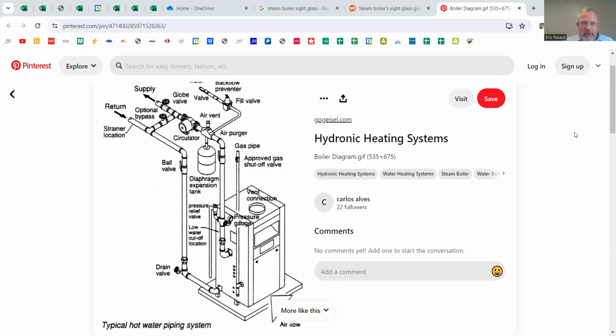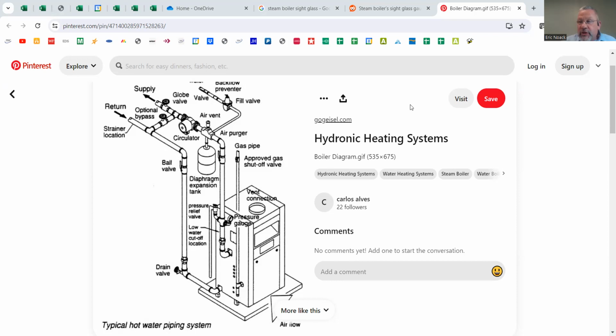And then you can look at certain circuits and really help your mind, or at least for me, it worked to simplify it in my mind and made it easier to look at. But the reason I'm saying this is a boiler is really no different than that wiring schematic. It's a piping schematic, essentially, right? So one of the things you're going to look for is at the very top here, where it says fill valve and backflow preventer. That's also referred to as a reducing valve. The reducing valve is the technically correct term for it.